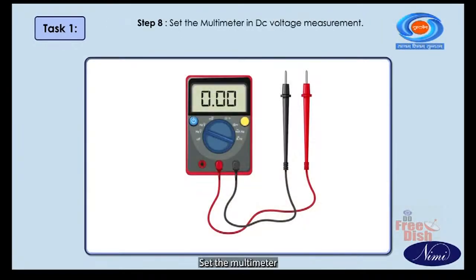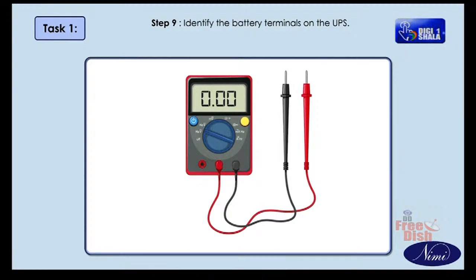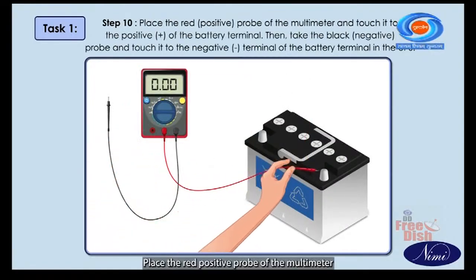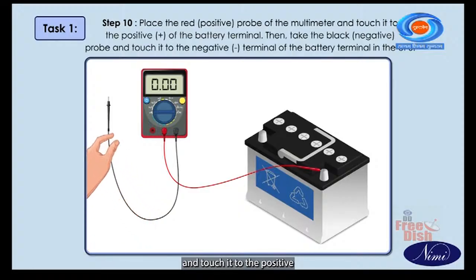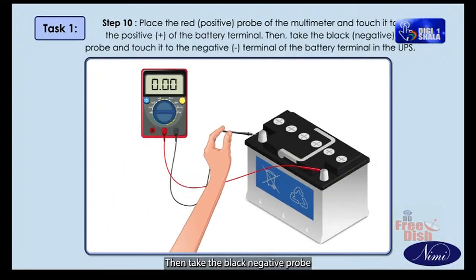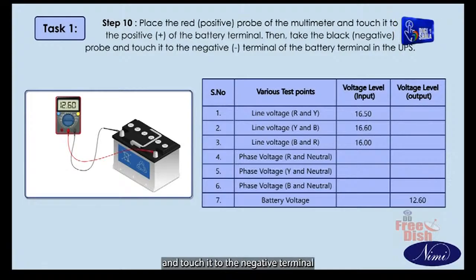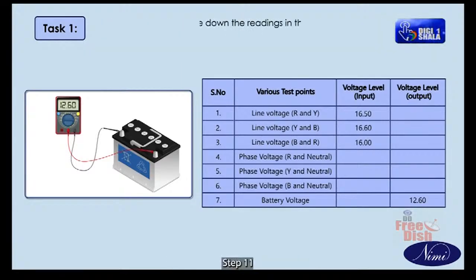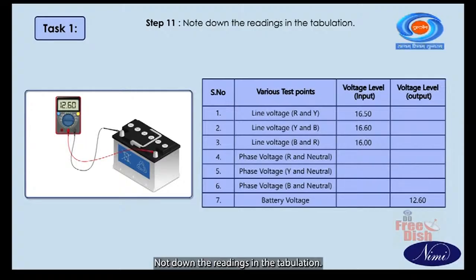Step 8. Set the multimeter in DC voltage measurement. Step 9. Identify the battery terminals on the UPS. Step 10. Place the red positive probe of the multimeter and touch it to the positive battery terminal. Then take the black negative probe and touch it to the negative battery terminal in the UPS. Step 11. Note down the readings in the tabulation.